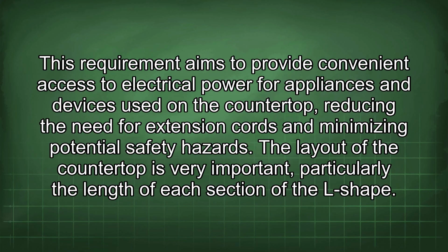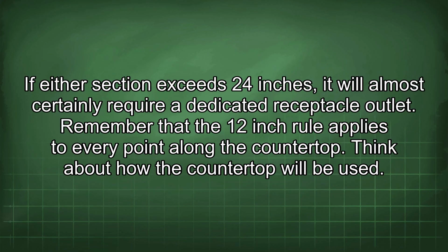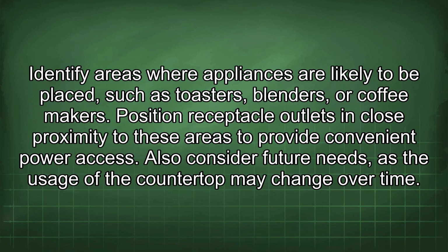The layout of the countertop is very important, particularly the length of each section of the L-shape. If either section exceeds 24 inches, it will almost certainly require a dedicated receptacle outlet. Remember that the 12-inch rule applies to every point along the countertop. Think about how the countertop will be used. Identify areas where appliances are likely to be placed, such as toasters, blenders, or coffee makers.